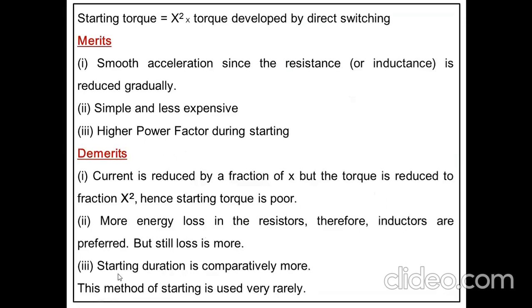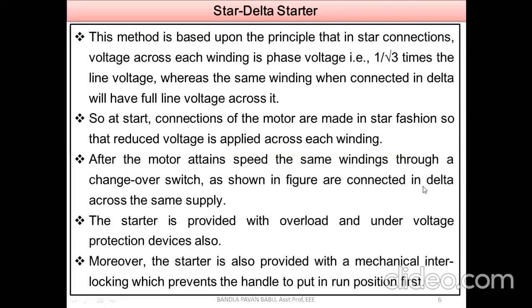Next, the starting duration is comparatively more. As I said before, we need to run the machine at its rated parameters, that means either rated speed or when it reaches the rated current. This duration will be more in this method, and that is one of the main drawbacks. That is why we are using this method rarely. Next, we'll discuss the star delta startup.